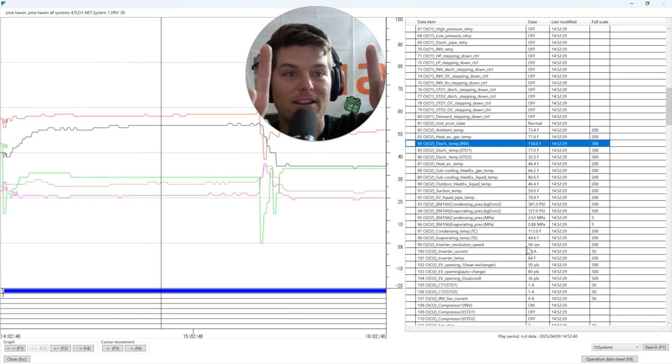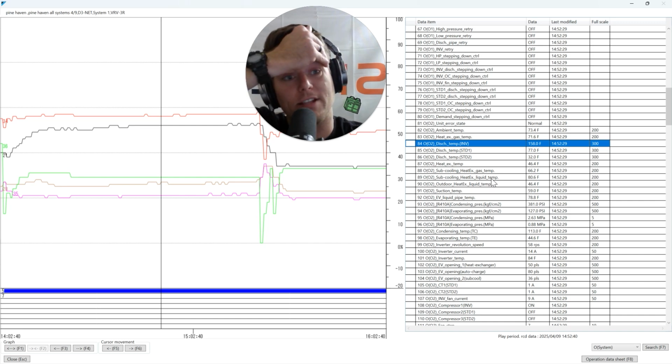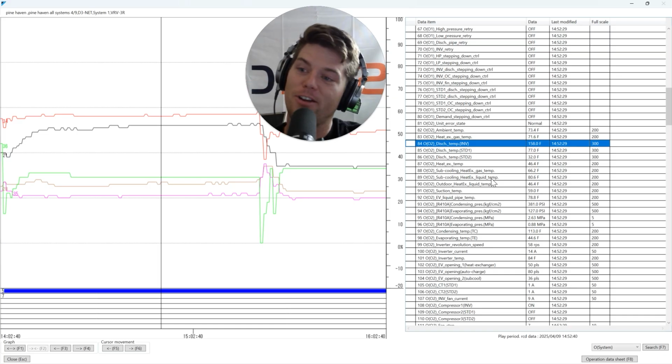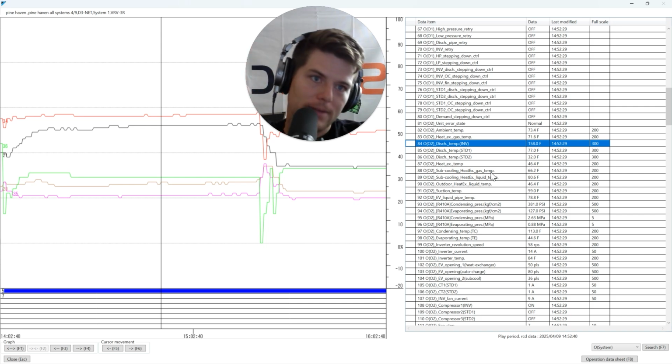So guess what? 1 + 1 is 2. That solenoid valve is probably bad, or it's doing something it's not supposed to. It's dumping something somewhere it's not supposed to. It's bypassing somewhere it's not supposed to. It's plugged into the wrong spot on the board, and when it's open, it's actually closed, and when it's closed, it's actually open. It's happened. Okay, they're different colored plugs, but they still fit in the same slots on VRV3. So, rant over. Let's jump back.